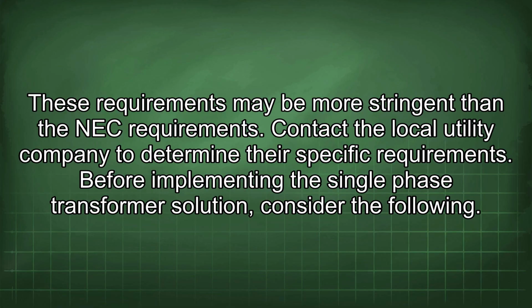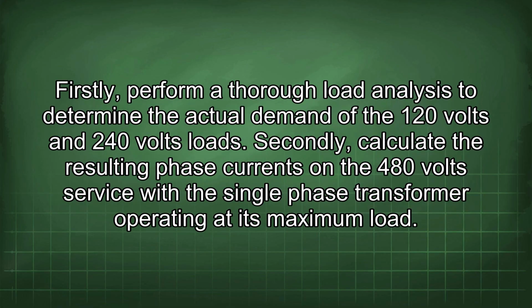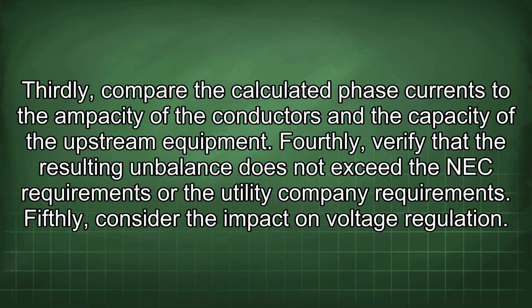Before implementing the single-phase transformer solution, consider the following. Firstly, perform a thorough load analysis to determine the actual demand of the 120-volt and 240-volt loads. Secondly, calculate the resulting phase currents on the 480-volt service with the single-phase transformer operating at its maximum load. Thirdly, compare the calculated phase currents to the ampacity of the conductors and the capacity of the upstream equipment. Fourthly, verify that the resulting unbalance does not exceed the NEC requirements or the utility company requirements.